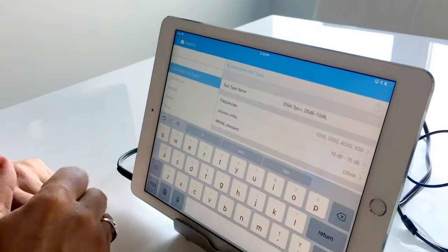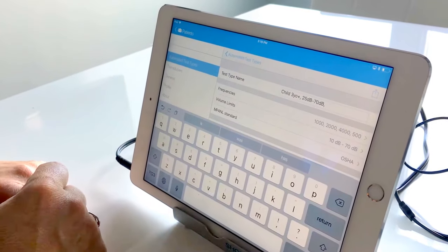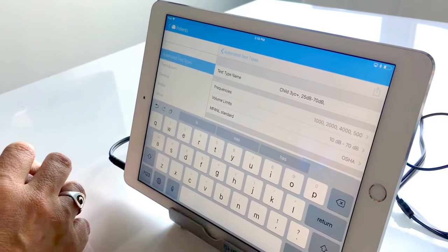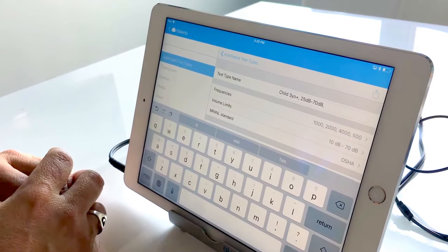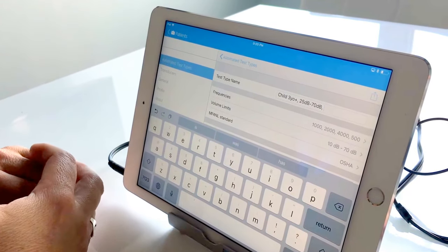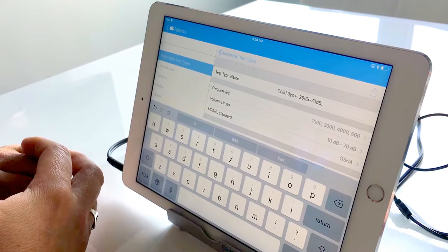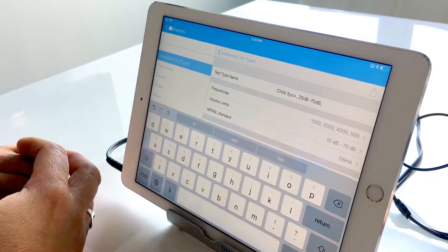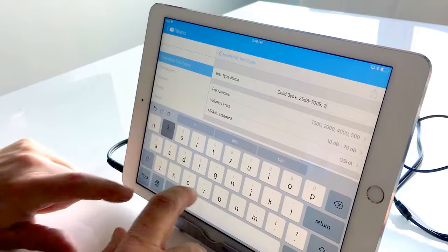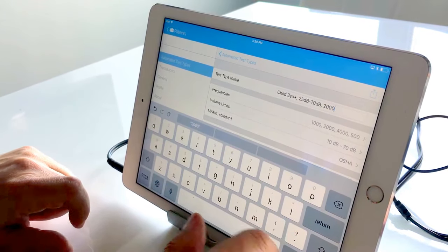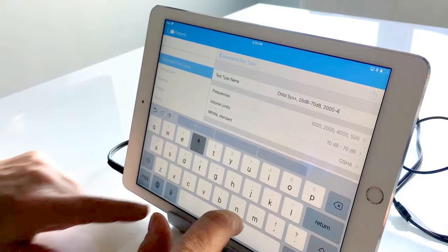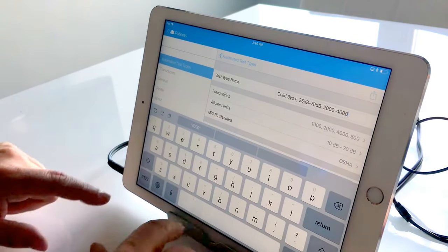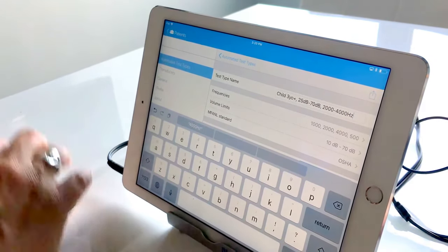The other thing that I'm going to put in the title is the actual frequencies that we're going to test. Because of the noise levels, I'm going to recommend that we leave off the low frequencies because that's often where the highest levels of noise are concentrated. So what I'm going to recommend is testing 2,000 and 4,000 hertz for this instance. So that's something that we would also like to put in the title bar. And you'll see why when we see the whole list.